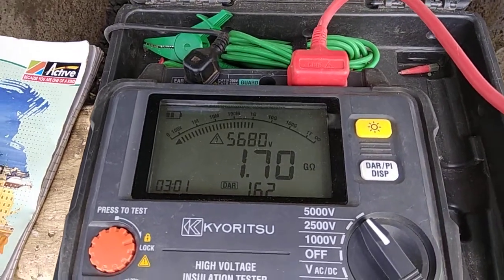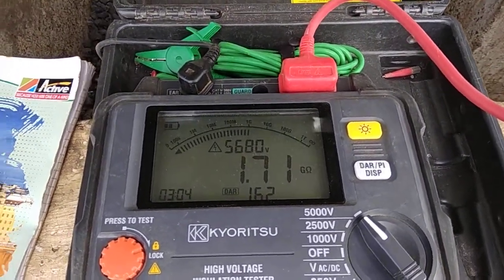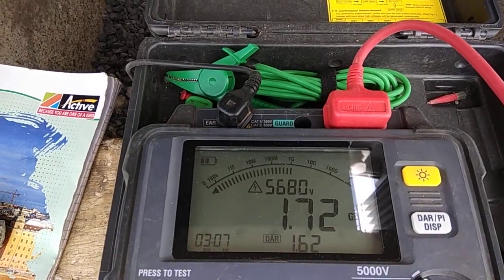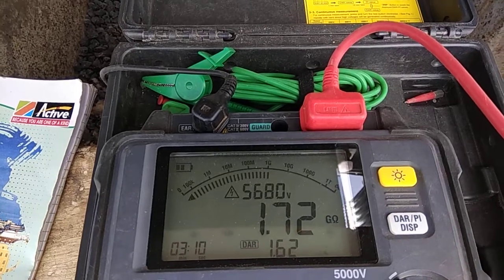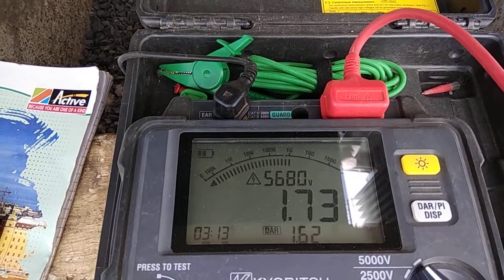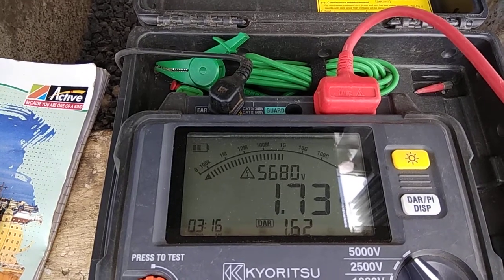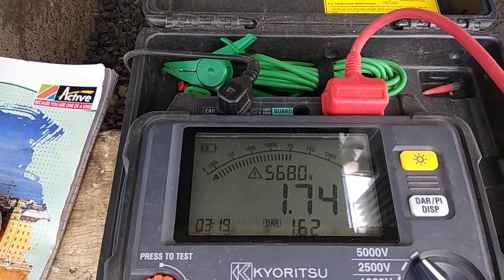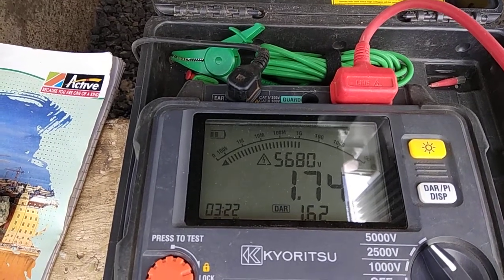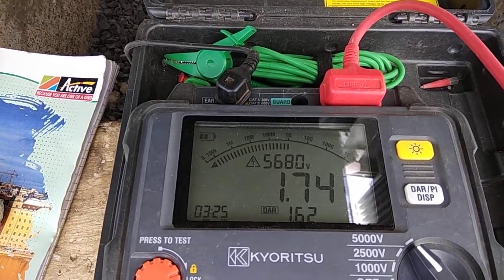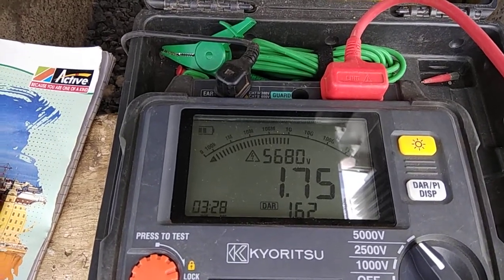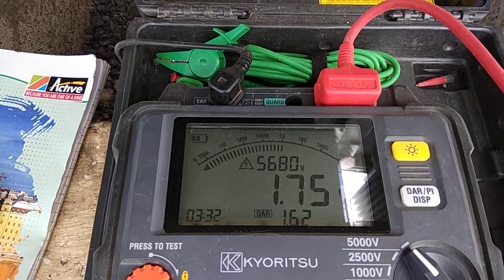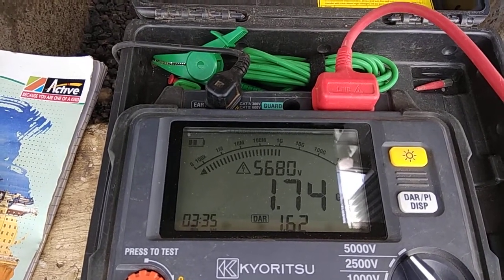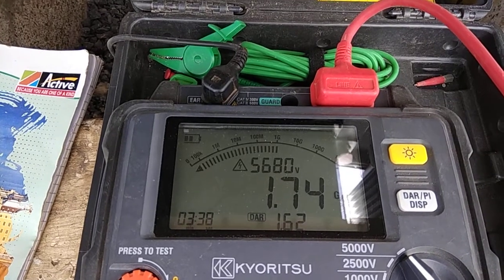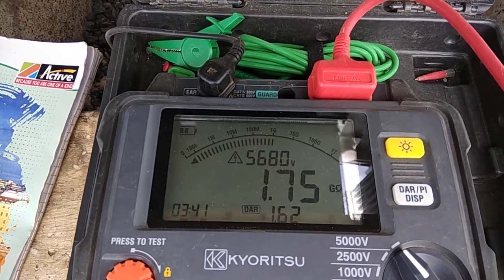Coming to the fourth point, that is the polarization current. I mentioned earlier that the insulator is hygroscopic in nature, so it absorbs moisture and dust particles. These particles, moisture and dust, are dielectric in nature. So when they are put in the electric field, because when we are injecting the voltage the electric field is generated there, these particles align along the direction of the electric field. There is energy required for the alignment of these dielectric particles along the electric field. This energy is taken from the voltage source in the form of current. So there is the polarization current, and this current remains in the circuit for at least 10 minutes.